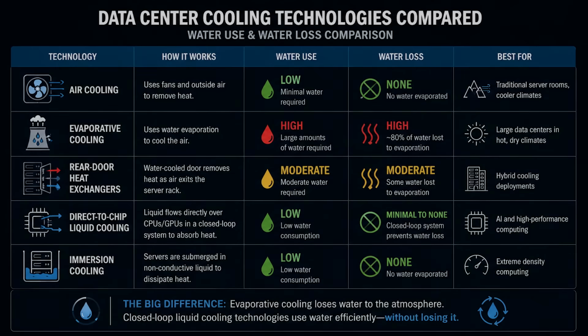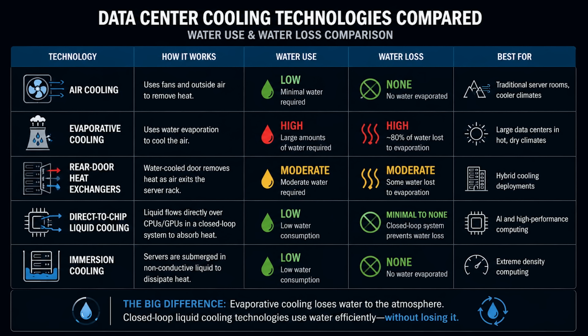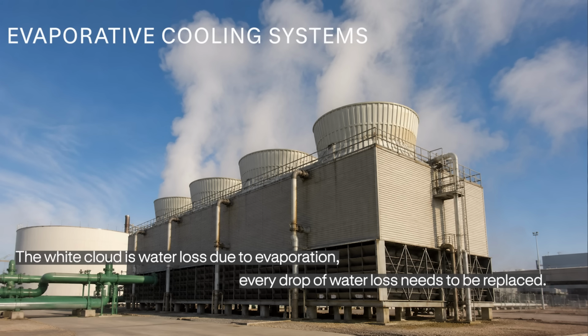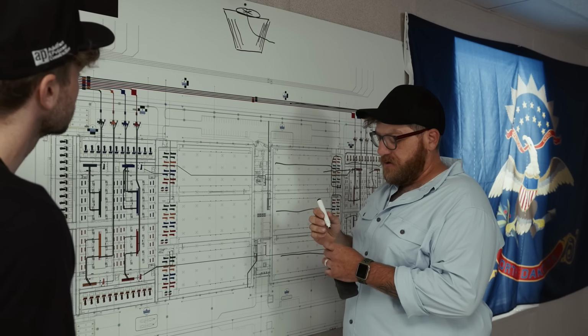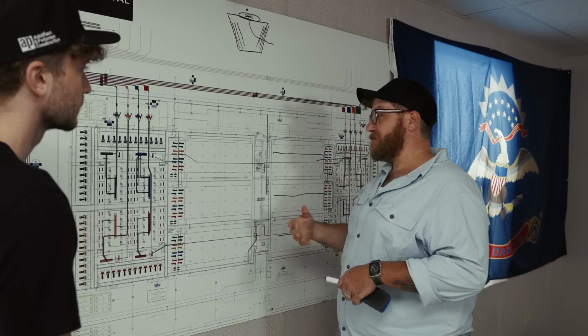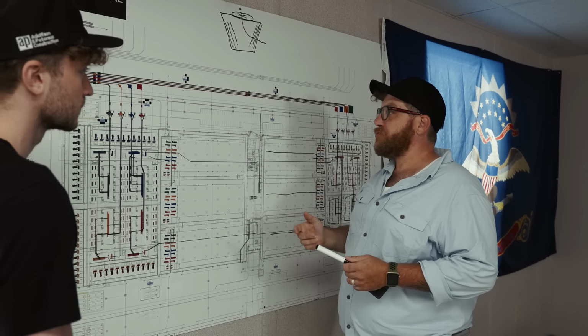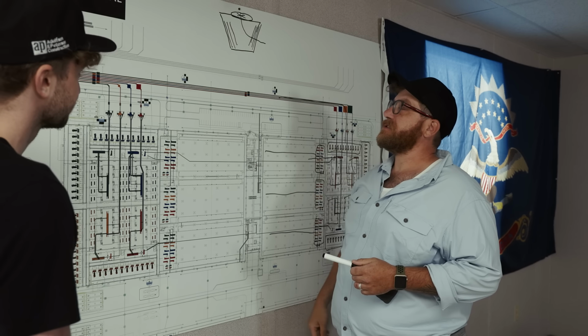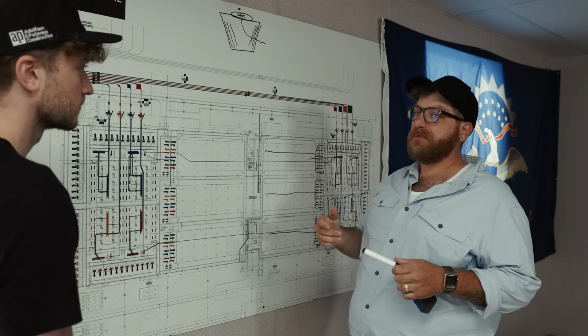Some data centers do consume significant amounts of water, but cooling systems are not all designed the same way. An evaporative cooling system, say, that uses 2 million gallons of water a year, just evaporates into the ether. With evaporative cooling, you put so much water vapor into the air, and it's all a matter of efficiency. So when you hear about buildings, specifically older data centers, consuming water, that's where a bulk of that consumption comes from, the evaporative cooling process.